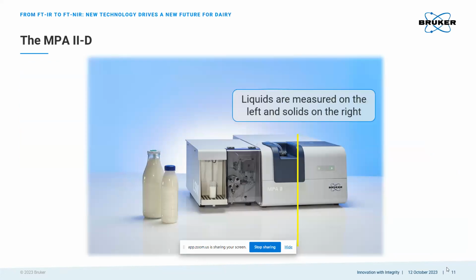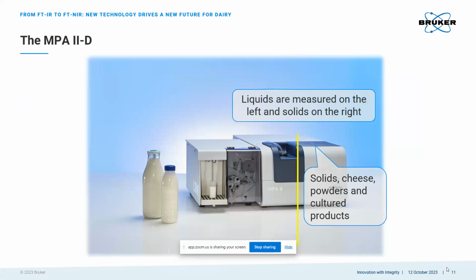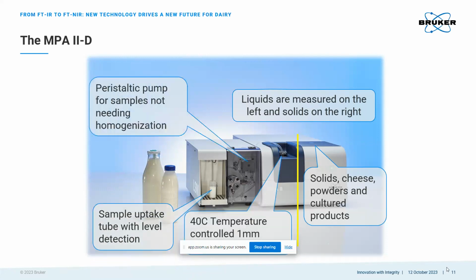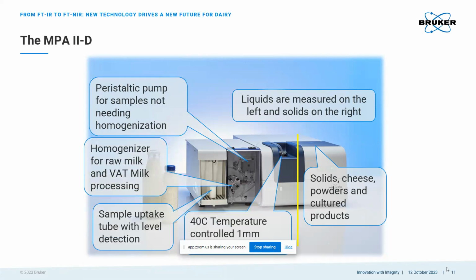So here's a breakdown of our MPA2D. On the right side of the instrument, we can measure solid and paste-like dairy products, whereby we can put on the integrating sphere module, which we can analyze our powder samples in cups, or in the case of our cheeses, those disposable Petri dishes that we talked about, or glass or quartz Petri dishes. On the left side of the instrument, we have the liquid sampling module, what I referred to as the LSM earlier, which is our dual system allowing either for the homogenation of a sample or a simple pumping through that 1,000-micron path length flow cell for analysis.